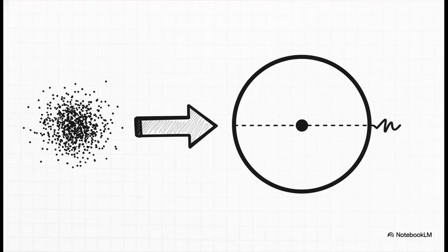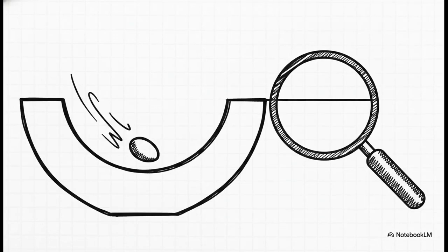Now, uncalibrated magnetometer data is, frankly, a mess. To fix it, the MATLAB script analyzes those sensor readings and uses linear regression to fit a perfect mathematical sphere right over the scattered data points. By hammering out the coefficients A, B, C, and D, the algorithm mathematically locks in the sphere's exact center, its radius, and the residue. Think of this sphere as your highly rigorous, mathematically pure baseline for calibrating the rest of the sensor. And the hard proof of that algorithm's accuracy?